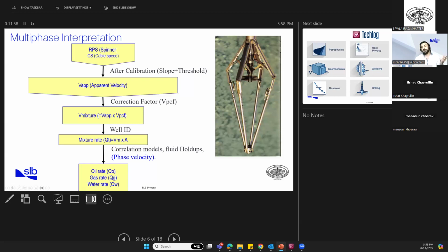Then from the mixture velocity, and with the ID from the caliper that already measured the wellbore, at the end we can have the total rate that we are producing. Then, by having correlations, and in the correlations we need to know the holdup for each phase, either oil, gas, or water, we can estimate the velocity of the water, oil, and gas. And then at the end, we're going to have the rate of each phase. So this is, I would say, the workflow that basically every engineer or every interpreter is using in order to end up with the quantitative measurements for the PLT.